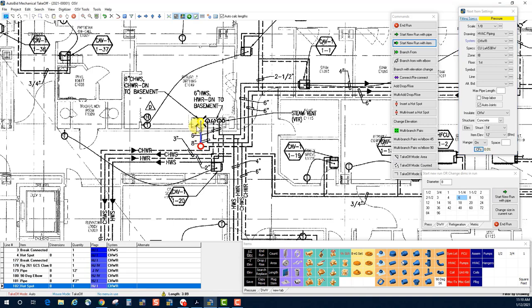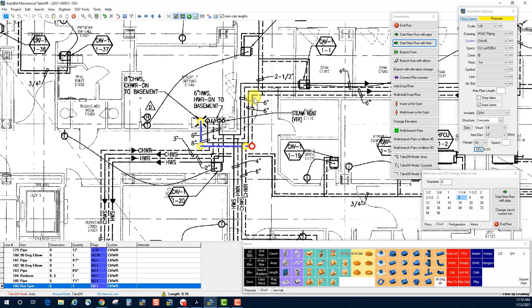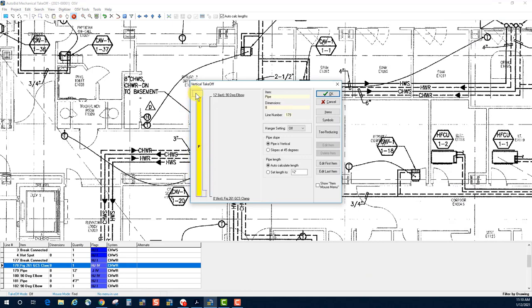As you go along, you'll see it puts the X in there, indicating a vertical. When there's a pipe size change — say to six inch — all you do is put the new dimension in the change dims field in the run, and it automatically puts the reducer in. Clicking on the X, we can see the vertical pipe from zero feet up to 12 feet, with an elbow at the top and a riser clamp at the bottom.